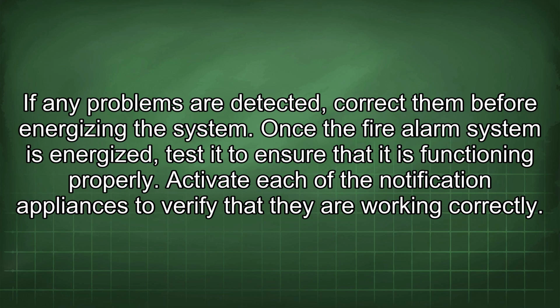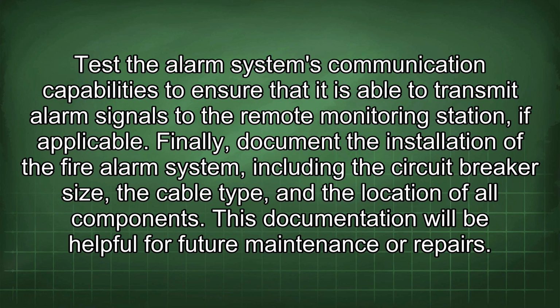Once the fire alarm system is energized, test it to ensure that it is functioning properly. Activate each of the notification appliances to verify that they are working correctly. Test the alarm system's communication capabilities to ensure that it is able to transmit alarm signals to the remote monitoring station, if applicable. Finally, document the installation of the fire alarm system, including the circuit breaker size, the cable type, and the location of all components. This documentation will be helpful for future maintenance or repairs.